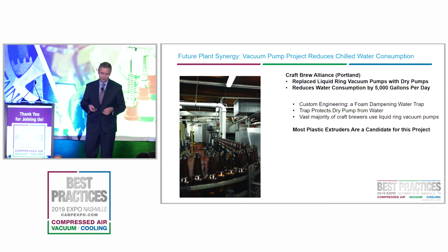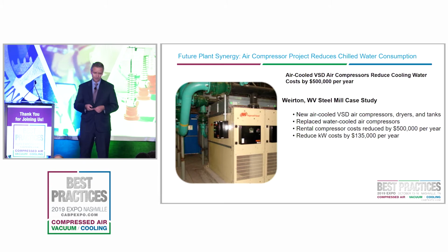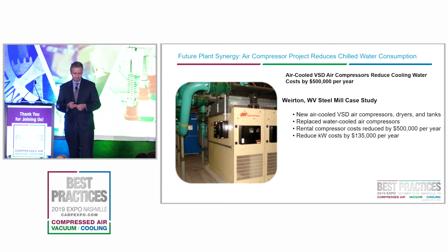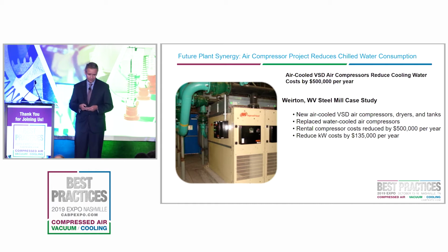I think a lot of this community is the best prepared for that because you've already gone down that journey. So here's a job in Weirton, West Virginia: air-cooled VSD air compressors reduce cooling water costs by $500,000. Basically, they were able to switch from water-cooled to air-cooled, and that's not an easy thing to do. We had a session yesterday about it, but let's challenge it and see what the benefits are. In this case, a new air-cooled VSD air compressor, dryers and tanks gave benefits which included knocking out $500,000 a year in rental compressors and $135,000 in kilowatts.